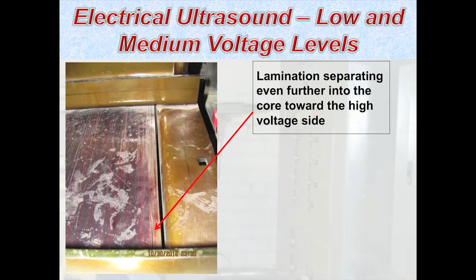So this is now looking more and more like the root cause of why we heard what we did. Even going in further, you can see the first part right here where it's separated. There's separation into the core toward the high side, the 12,000 volt side. And this immediately looks like what? If the unit's only 5 years old and this is going on, what do you suspect? It's a defect. But manufacturers never have defects, do they?